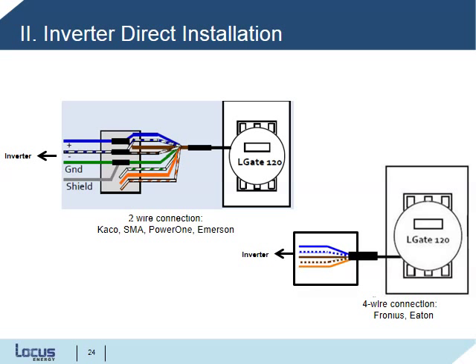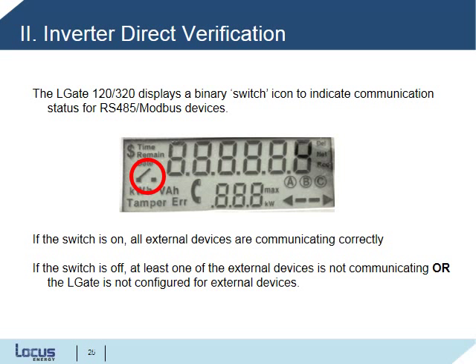For 4-wire connection methods, such as with Fronius and Eaton inverters, wire the blue, blue-white, brown, brown-white, and orange wires to the inverter. After setting up these connections, you can verify inverter direct connectivity by checking the binary switch icon on the LCD screen. This icon, shown here circled in red, indicates communication status for all RS-485 and Modbus devices.